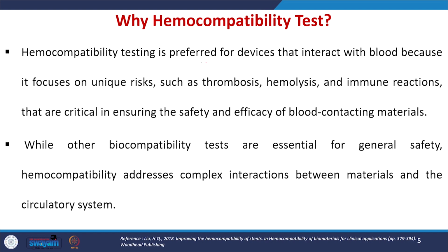Let us see why to do hemocompatibility test. Hemocompatibility test is very important for biomedical devices and implants that interact with the blood because it focuses on unique risks such as thrombosis, hemolysis and immune reactions. So, that is why the hemocompatibility test is very important to understand the safety and efficacy of the blood contacting materials. The other biocompatibility tests mainly focus on the general safety of the particular material, but the hemocompatibility mainly focuses on the interaction between the materials and the circulatory system.